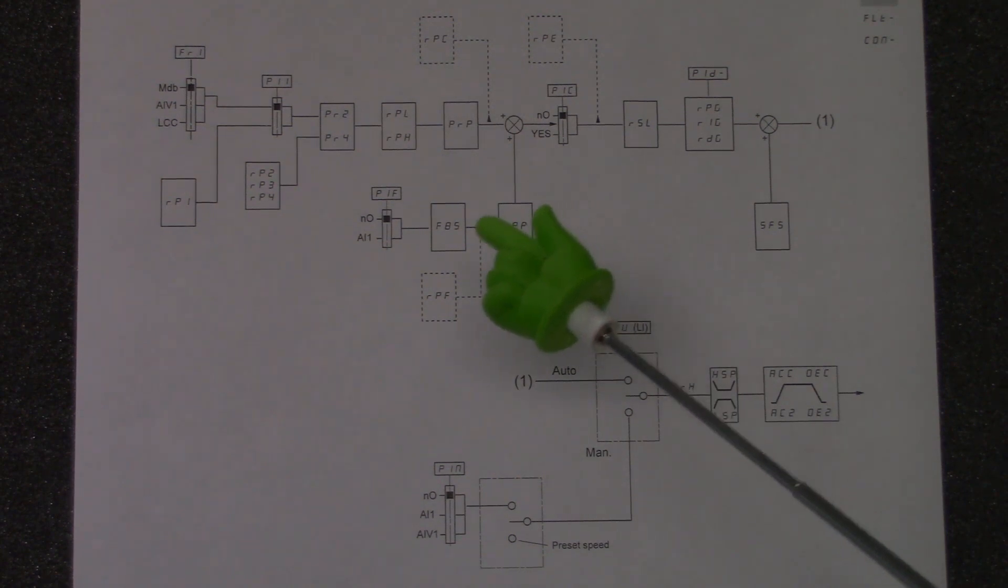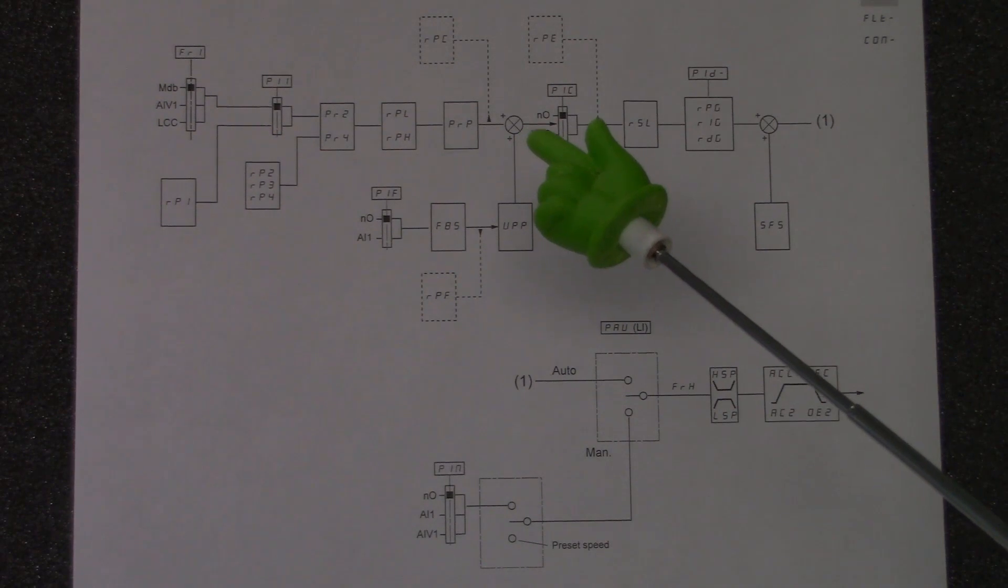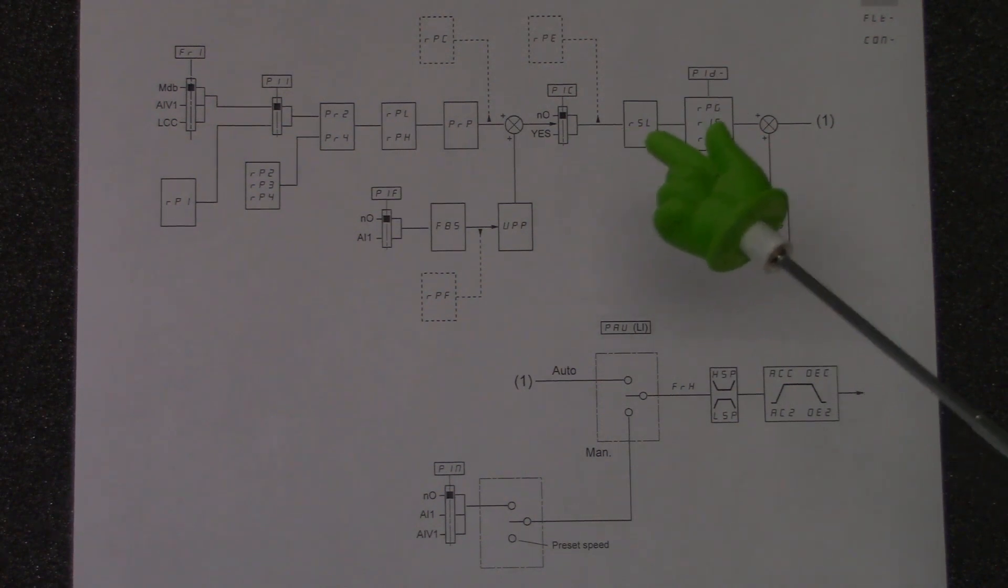And this is where we select our return from. The PIF parameter only having NO or AI1 as the selections. We then go into the error inversion loop. And then from there to the sleep and wake up values set inside the drive if required. We then have our normal gains.